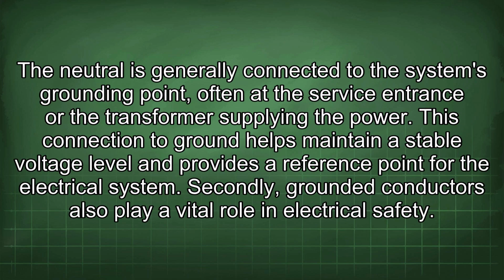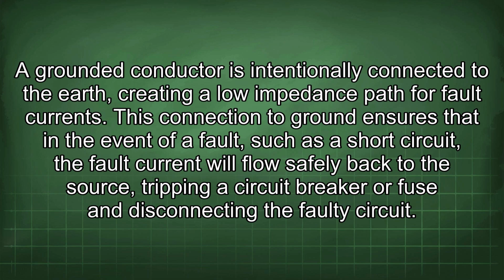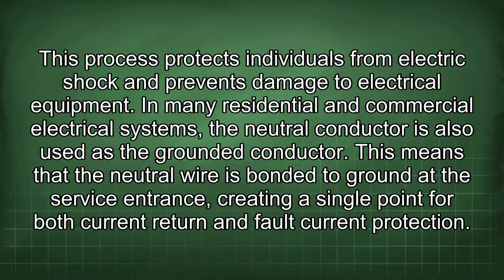The neutral is generally connected to the system's grounding point, often at the service entrance or the transformer supplying the power. This connection to ground helps maintain a stable voltage level and provides a reference point for the electrical system. Secondly, grounded conductors also play a vital role in electrical safety. A grounded conductor is intentionally connected to the earth, creating a low impedance path for fault currents. This connection to ground ensures that in the event of a fault, such as a short circuit, the fault current will flow safely back to the source, tripping a circuit breaker or fuse and disconnecting the faulty circuit. This process protects individuals from electric shock and prevents damage to electrical equipment.